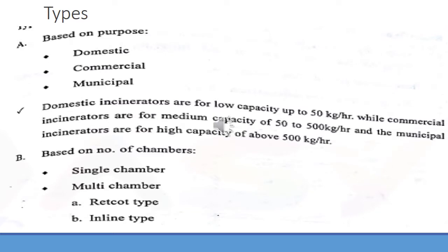Moving on to the types of incineration — there are different types based on their purpose. It can be domestic, commercial, or municipal. A domestic incinerator is used mainly for domestic purposes with a very small capacity of about 50 kg per hour. A commercial incinerator is of medium capacity, up to 500 kg per hour. A municipal incinerator is for high capacity, above 500 kg per hour.